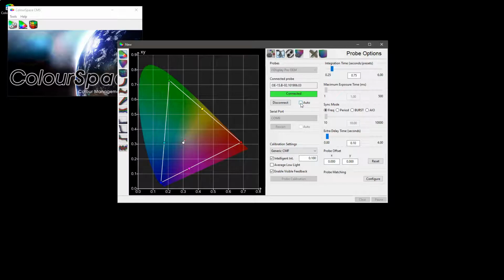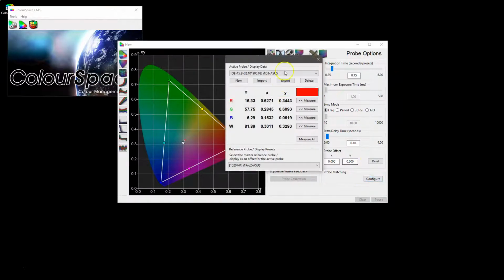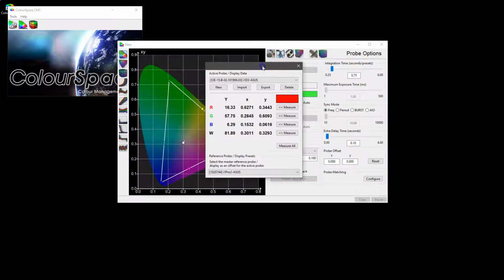to the ColourSpace PC. The next option that we have are the calibration settings, which are preset matrices for the connected probe, assuming it has them, and these are held within ColourSpace itself, and you can select the one that best matches the display technology that you are working with. We tend not to use these, as we tend to prefer using probe matching, because it gives a far more accurate result than using what are basically generic presets.